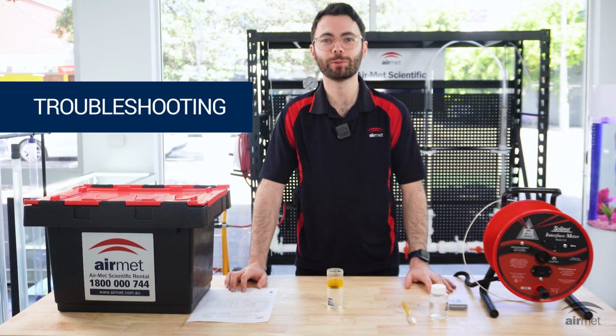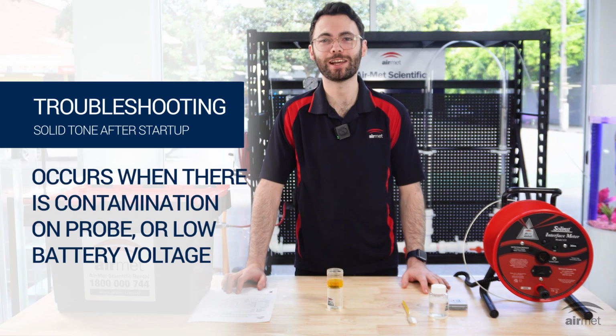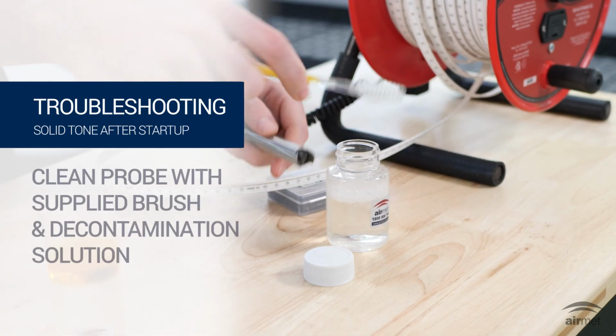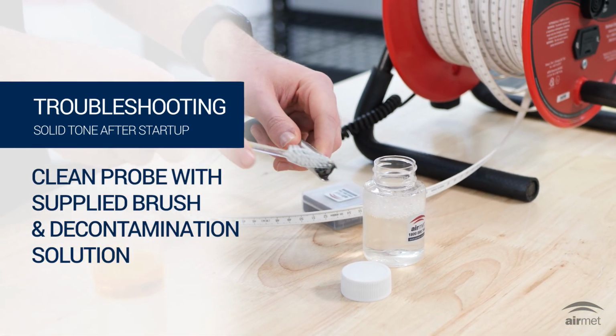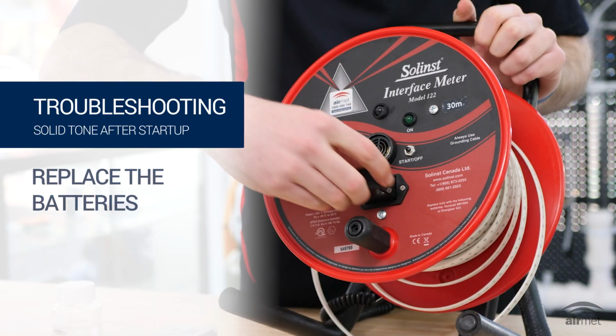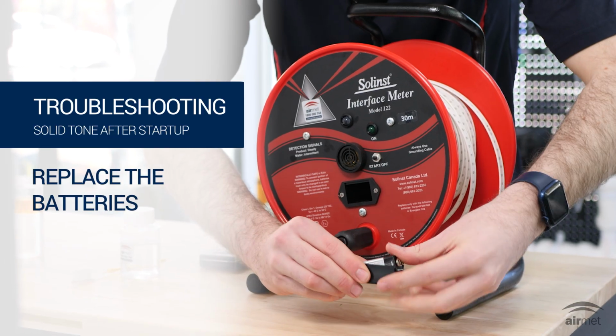Finally, let's review some troubleshooting tips for the Solinst 122 to help you identify and fix any issues you may have during use. Solid tone after startup. This occurs when there may be contamination on the probe or when the battery voltage may be too low. To resolve this, clean the probe with the supplied brush and decontaminant solution and replace the battery using the spare 9-volt batteries.